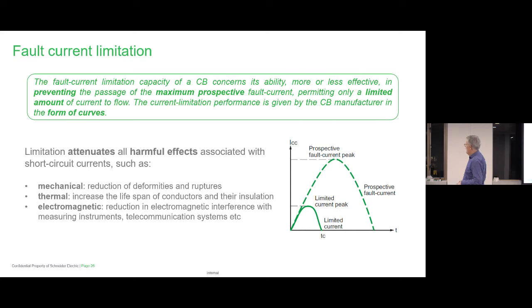So what this diagram is really showing us is what can happen if you don't have a fault limiting breaker. You can see a prospective fault level peak of multiple times the prospective fault itself. So it's a massive amount of current. We don't want that to happen. Why? Because it's going to affect cables, insulation in a thermal sense. It's going to affect the mechanical aspects of it.